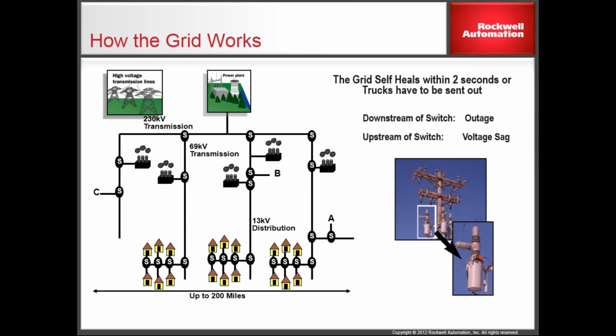We're going to have a little frog legs today, and we're going to open that line up so the frog can drop down where we can get him. And then we'll close the line a third time, and at that third try, if the short's still on the line, that breaker's going to pop open and stay open. Now, typically, these three events happen in about 2 seconds of time. There is some adjustment to it, and it can be set to 4 or 5 tries. And in some parts of the country where we're a long ways from service, they do that, right? Because if at all possible, we want to clear the problem without sending trucks. But once it's an outage, now they're going to send the trucks, right?